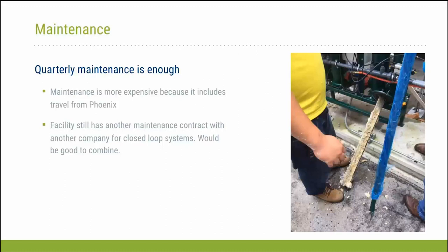And then once the system was in place and there wasn't a whole lot of makeup being brought in because we're running at a higher COC, they felt that our cleanings might be able to go every 4 or 5 months. And that still might be achievable with consistent regular cleanings and better control of the system. But right now, at least for us, a quarterly maintenance schedule is probably ideal, and it's safe. In that particular photo, you can see one of the insert rods before we started to clean it.